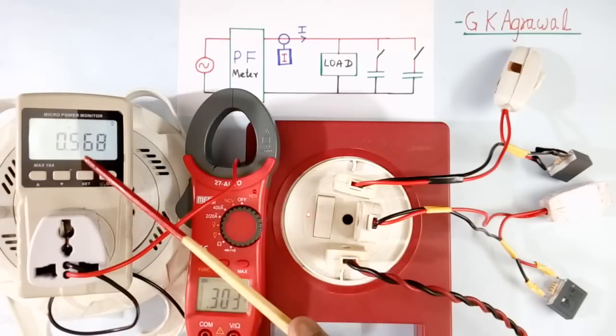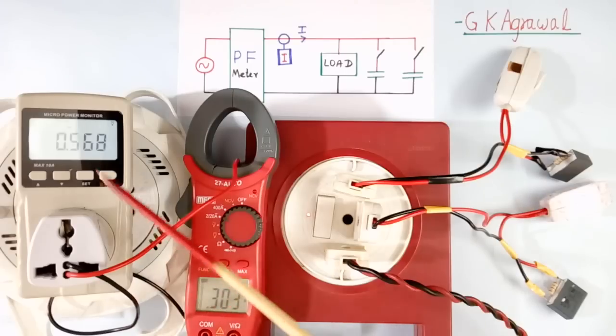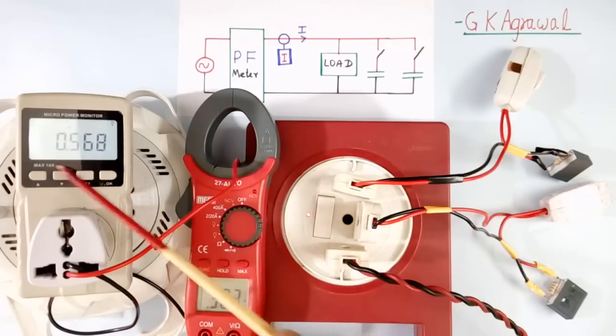You are seeing power factor of tube light is 0.568. And current is 0.3 ampere. It is very bad power factor.